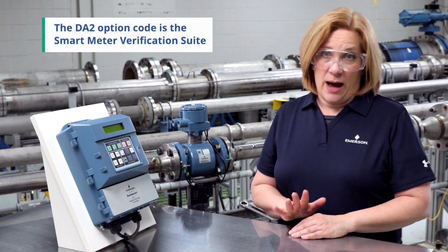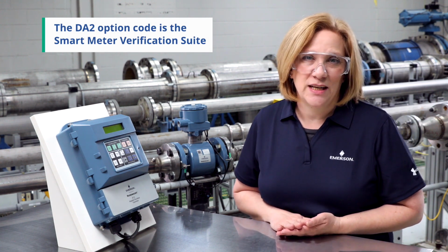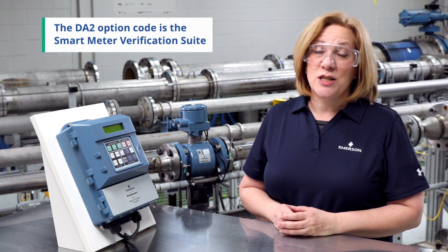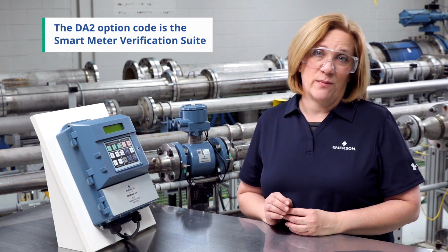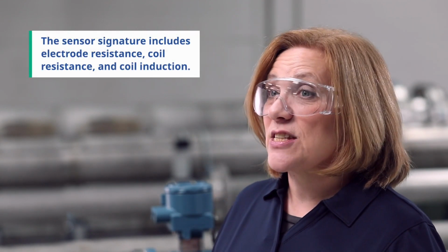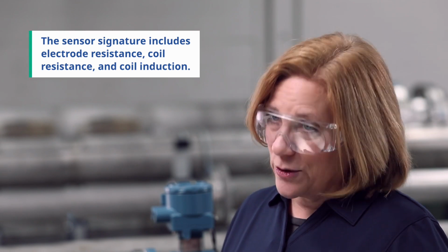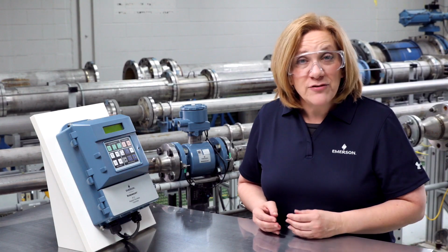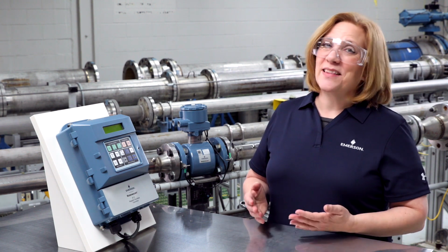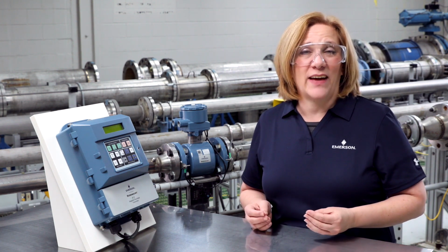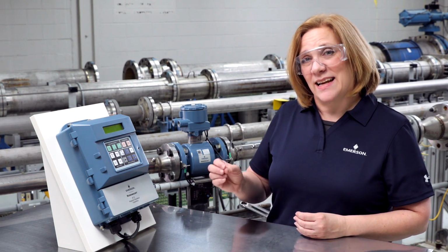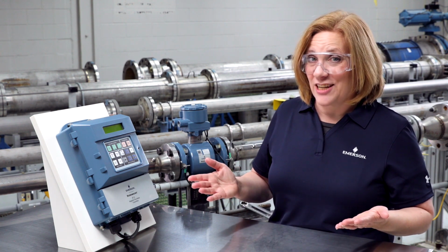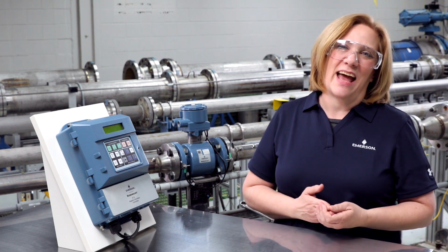The DA2 option code is the Smart Meter Verification Suite, which enables you to verify that your flow meter is within calibration without removing the sensor from the process. The first step is to establish a sensor baseline signature of the parameters that make up the strength of the magnetic field. The sensor signature includes electrode resistance and coil induction. After the baseline signature is established, you can run the smart meter verification test and compare the values that are measured to the original baseline signature. If these parameters have not changed, it indicates that the meter is still within calibration.